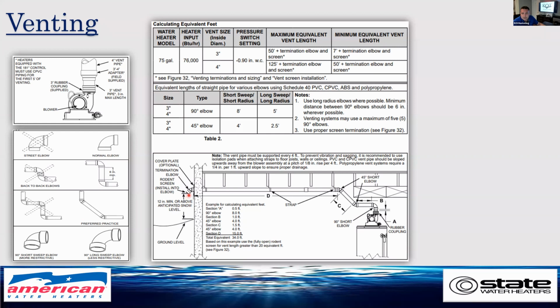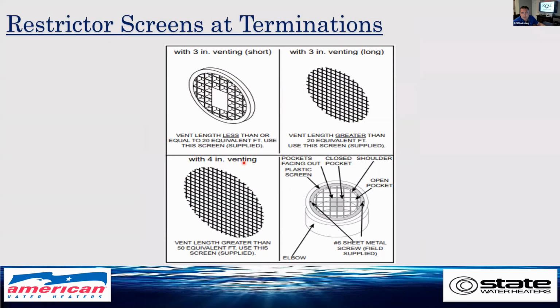That's also where the restrictor plates go. So our restrictor screens inside these venting terminals are located in the bag with the heater. It's important to install the correct restrictor. Too much back pressure can cause the pressure switch on the blower to fail, or the flame to be pulled off the burner and the flame sensor to deactivate.